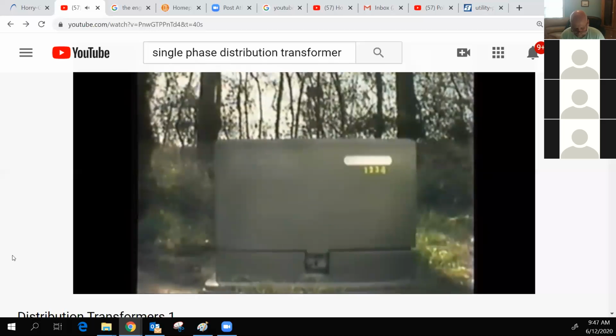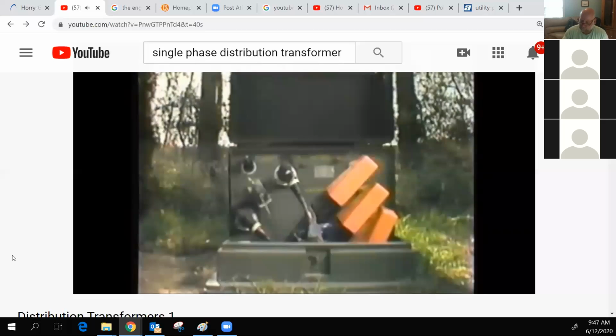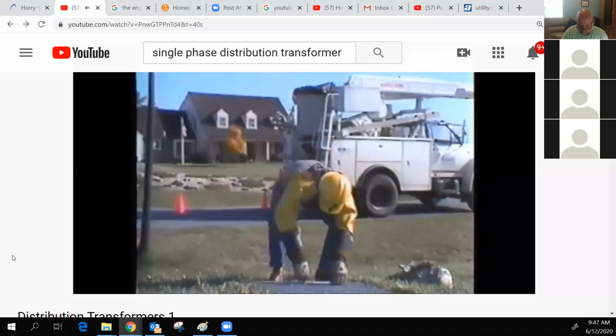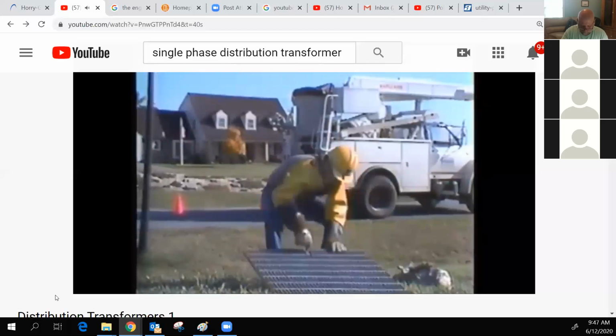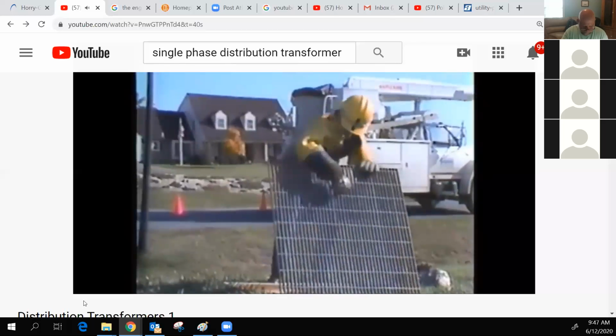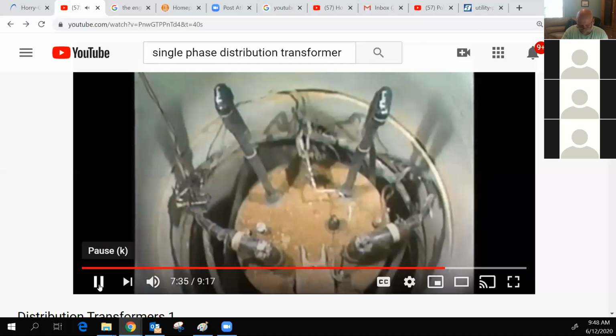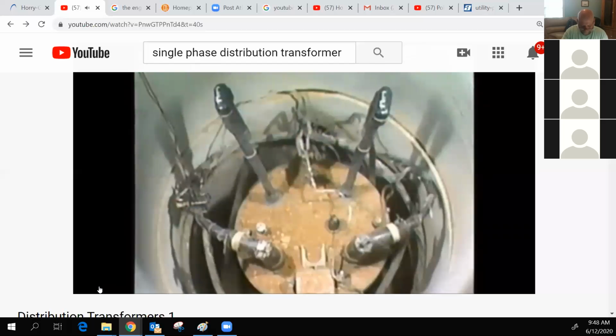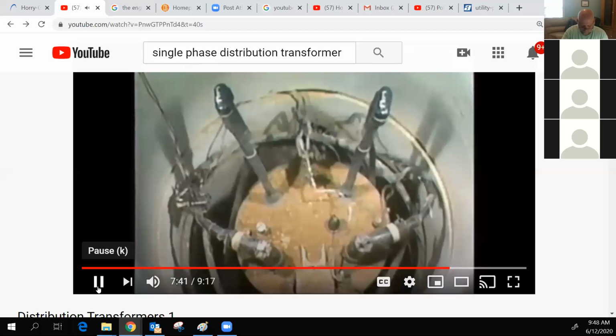Single-phase pad-mounted transformers are similar in shape, but their cabinets are usually smaller in size. Inside the cabinet are the primary bushings and the secondary bushings. Somewhat less common, but still used in many underground distribution systems, are subsurface transformers. Subsurface transformers are installed underground in specially constructed vaults for protection. In shape, subsurface transformers resemble single-phase pole-top transformers. However, both the primary and secondary bushings are usually located on the top of the transformer housing.